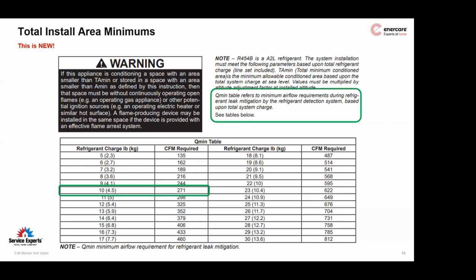Goodman handles this a little differently, especially with their TA minimum chart that we just covered. Instead of using pounds, they use a tonnage. So for instance, if you had a 1.5 ton piece of Goodman equipment, or Daikin or Amana, they would say you require 200 square feet or 180 square feet minimum. Lennox uses, and Carrier uses, per pound, basically 15 square feet minimum per pound. Basically that provides enough dilution so that it can't actually ignite in the space that it's in. And then if, God forbid, there's ever a leak, we do have a minimum CFM required in order to dilute the refrigerant throughout the conditioned space so that it doesn't ever become concentrated enough that it will actually ignite.